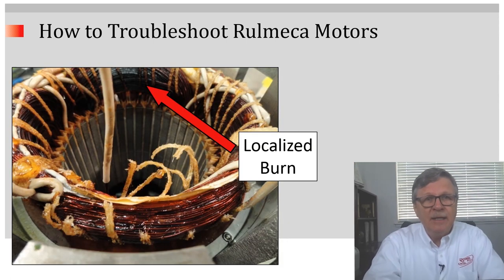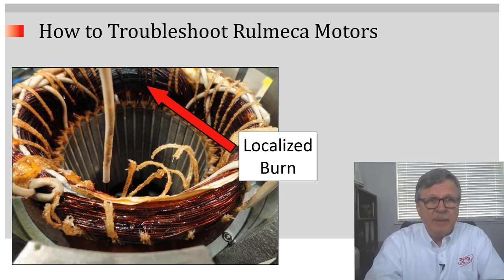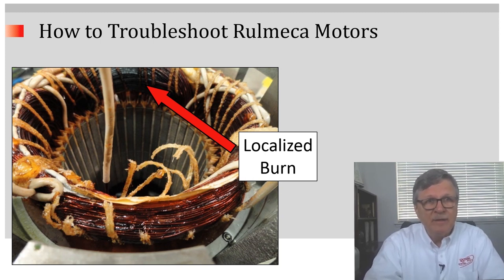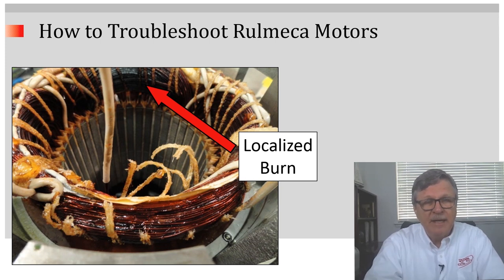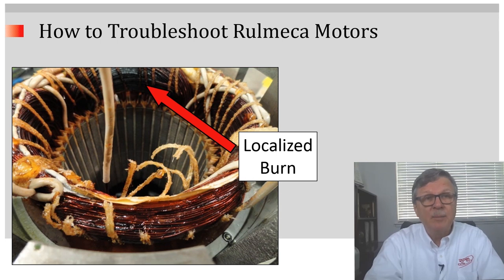Finally, this is a localized burn caused by a phase imbalance or single phasing. Notice that one of the phases — at the top of the screen where the arrowhead is pointing — is burned, while the other two phases still have a bright copper color.